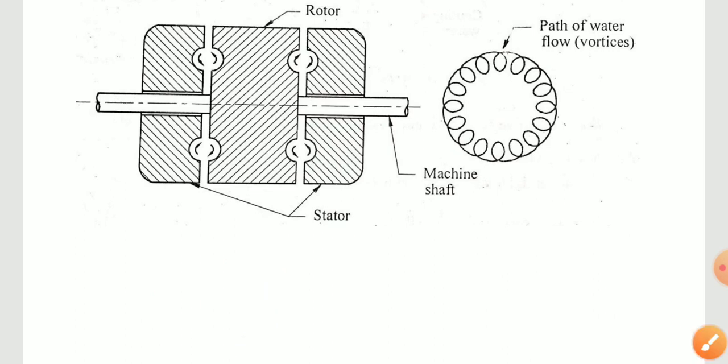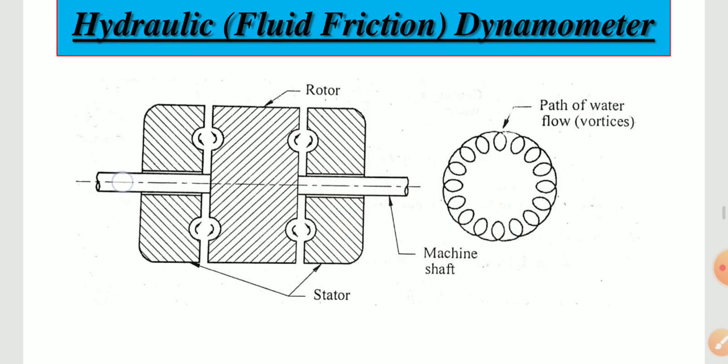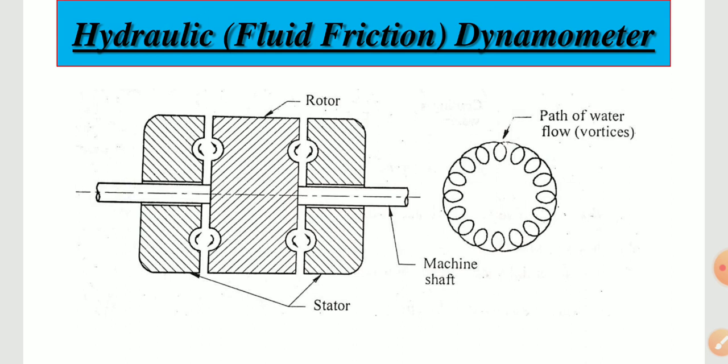The hydraulic dynamometer may be used for power up to 20,000 kilowatts and speeds up to 10,000 RPM. Advantages include: it can be used for high power measurement at high speed; water supplied serves two purposes — providing braking action and cooling; and it has high absorption capacity in a small space at low cost.